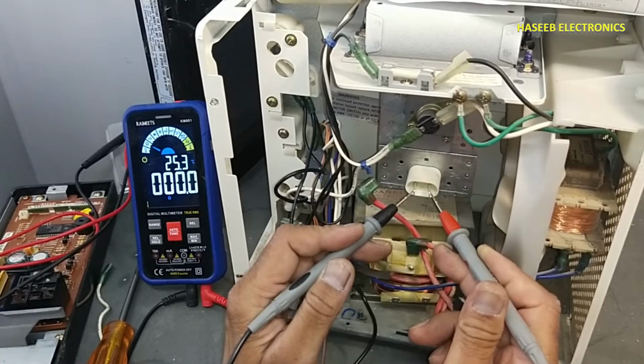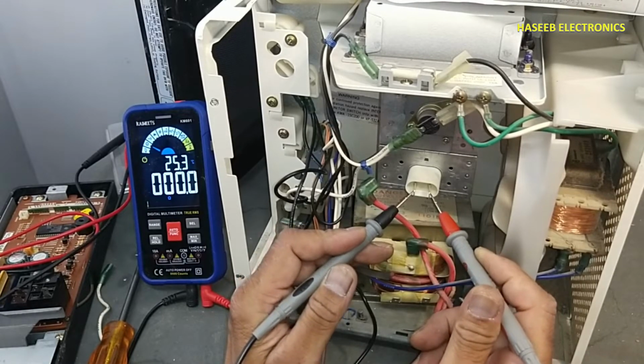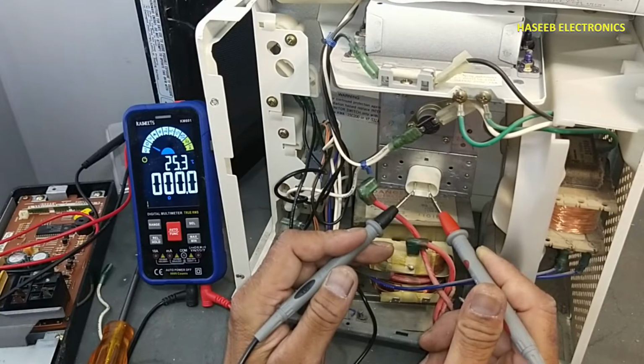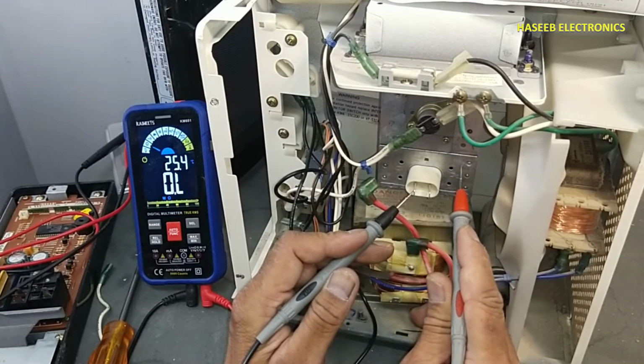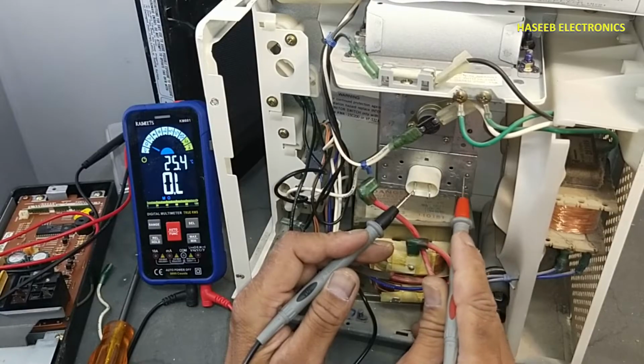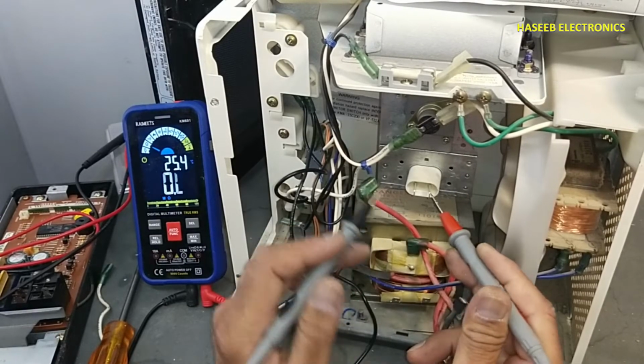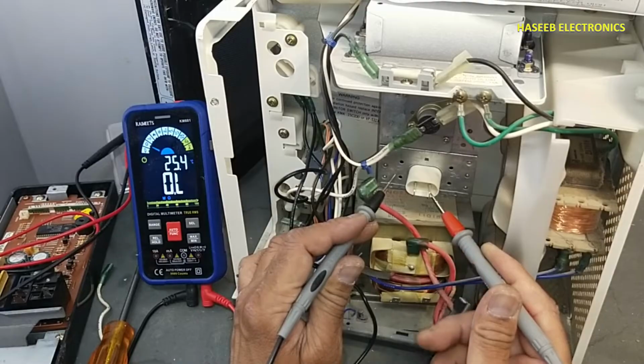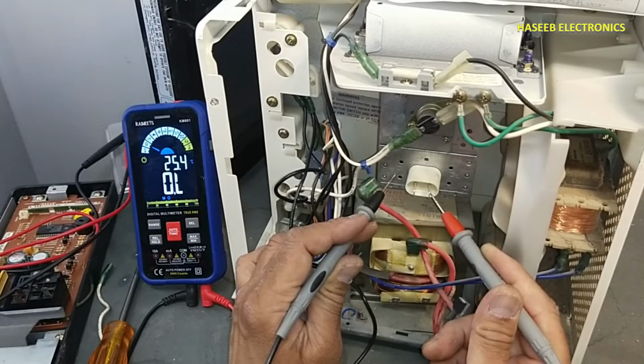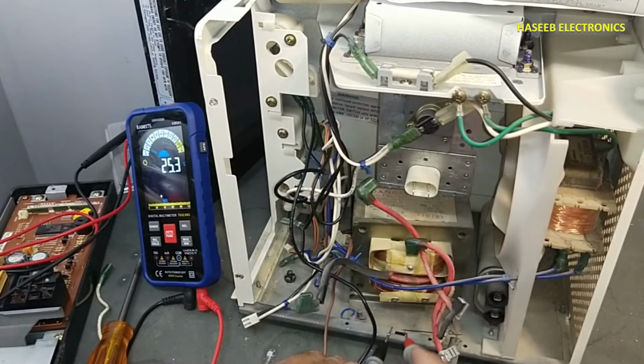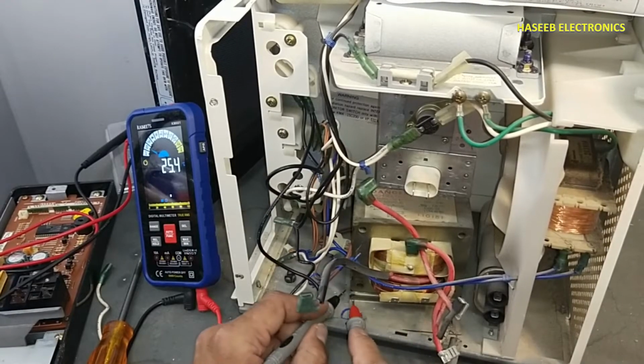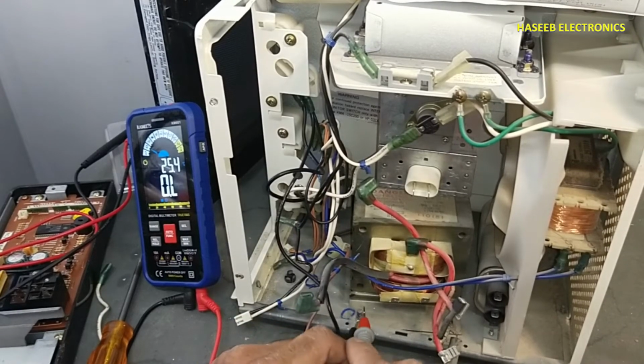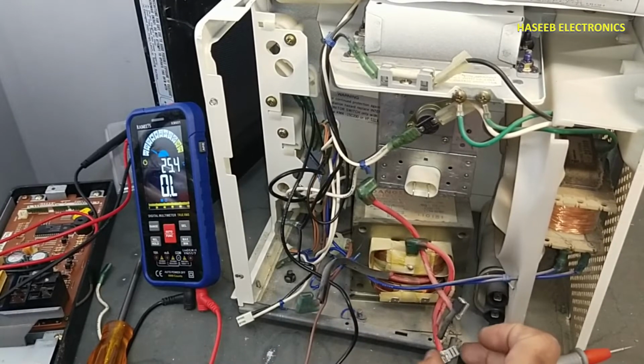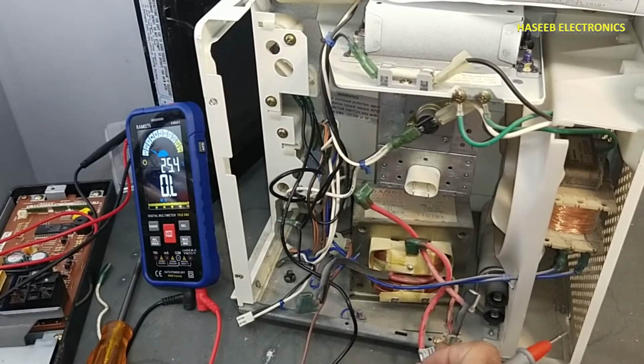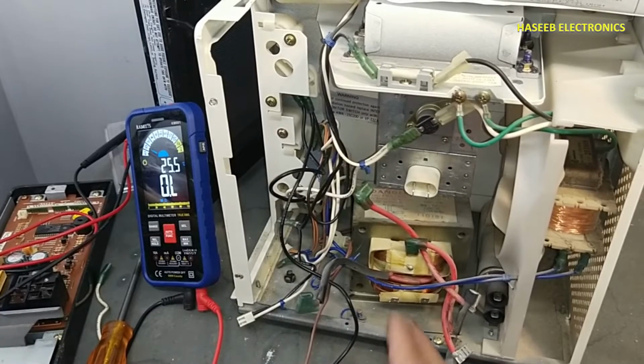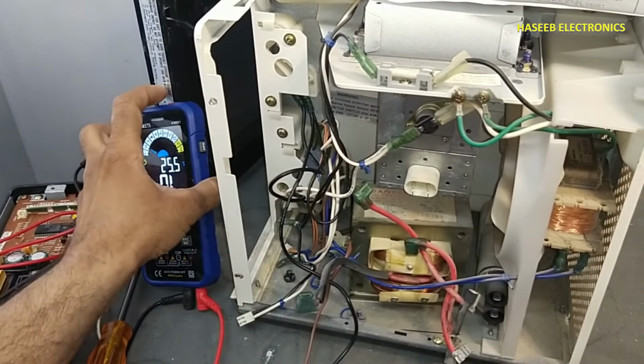Connect between these two terminals. It will give low resistance, less than 1 ohm. Check between chassis. It must provide high resistance. Check input terminal and chassis. It must be high. Its body must connect with this body, that is connected with the transformer, because one end of this high voltage wire is connected to ground, so it must be connected to chassis.